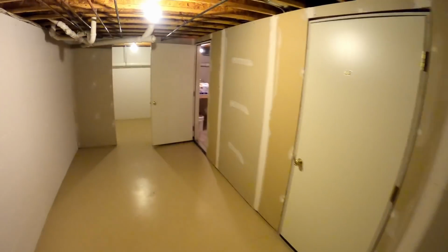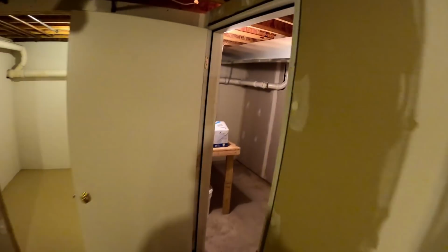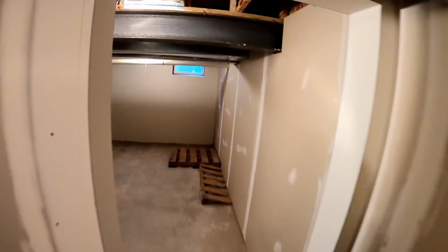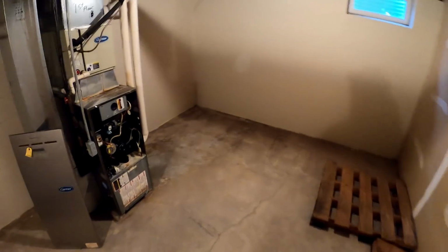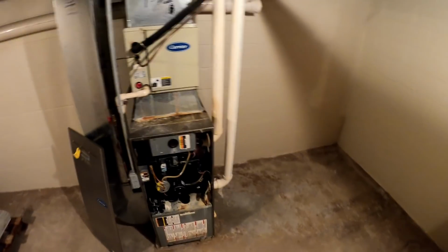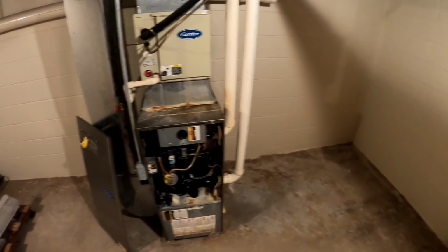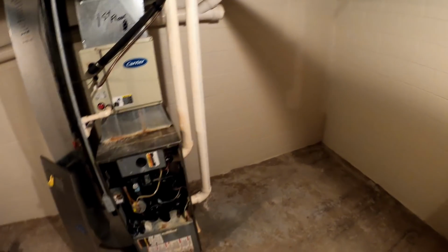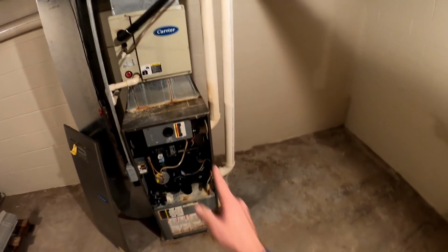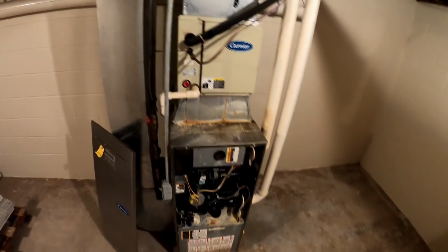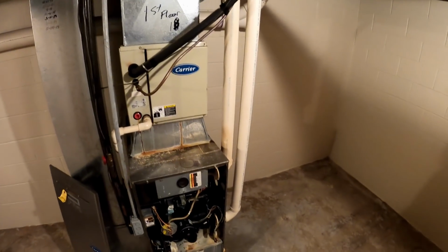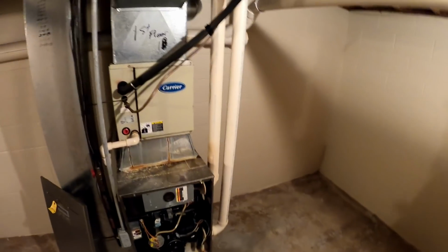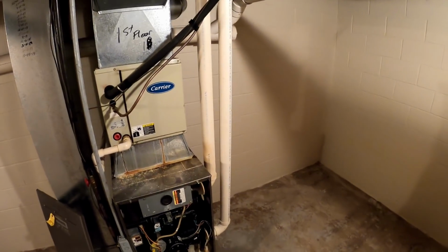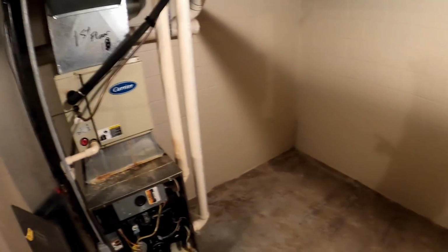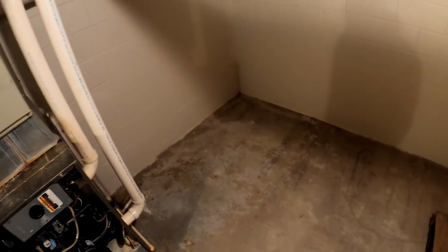Oof, and it smells nasty. Nasty. But quick diagnostic on these older carriers, it's one of the things you look for on a bad heat exchanger. It's that the limit is tripped. Guaranteed it's a bad heat exchanger, 9 times out of 10. Or 9.8 times out of 10. Could be other stuff, but I go just by the way it smells outside, and it's just done.